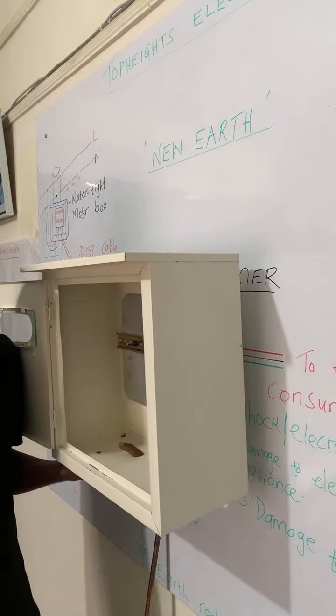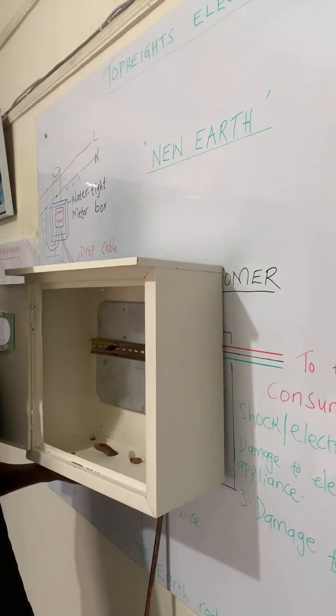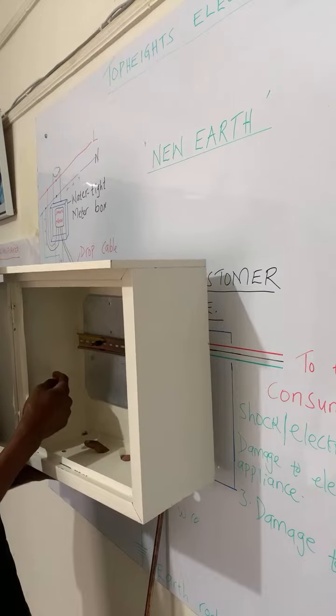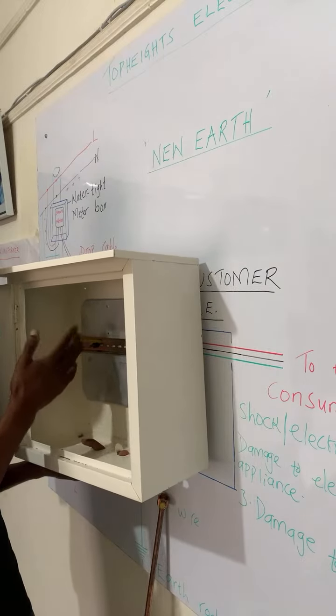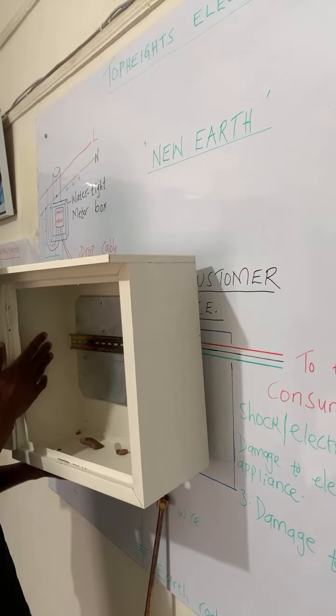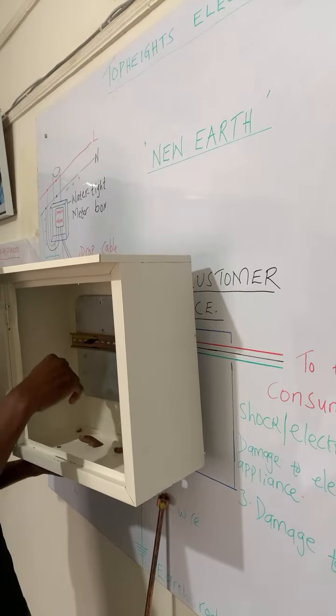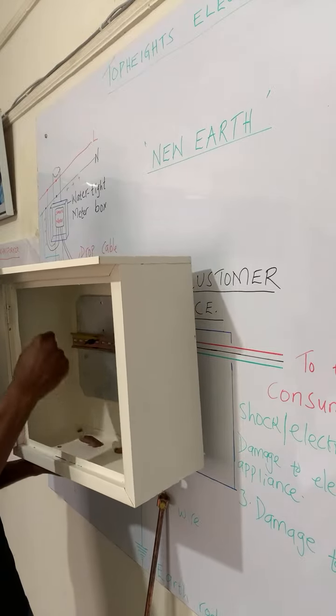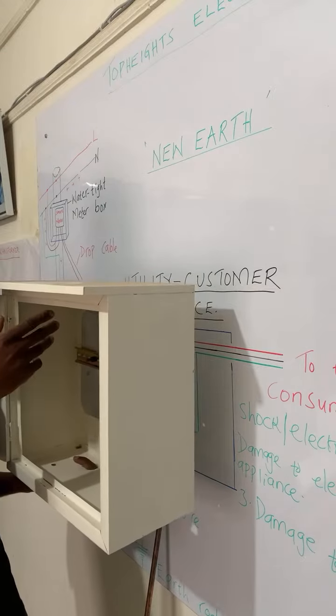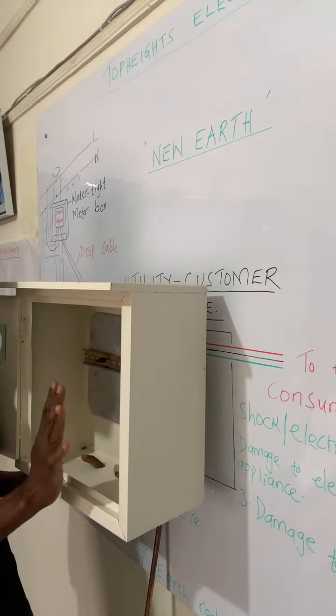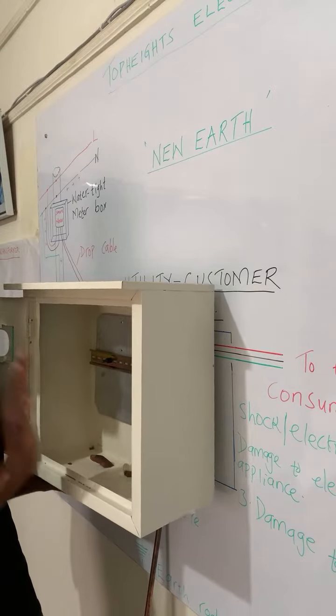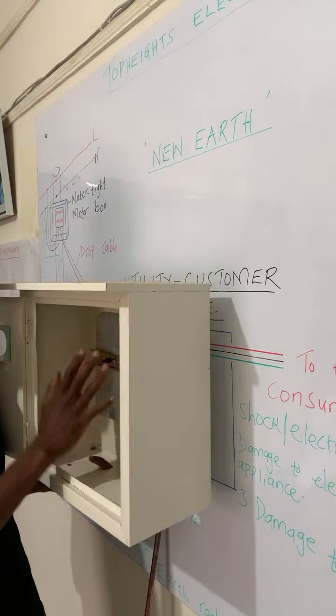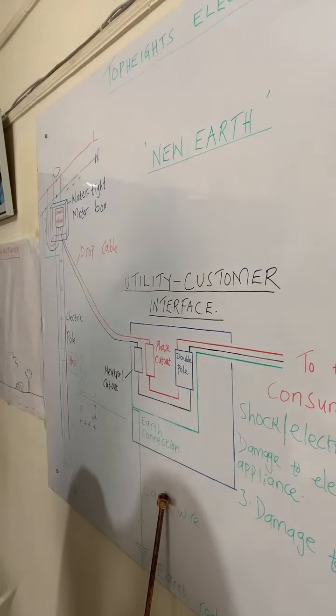Okay, so the earth connection will be started from the metallic point of the meter box, and then all the way to the earth rod, and then from there it will go direct to the consumer unit. So the neutral and the earth connection will not be bonded in the meter box or in the consumer unit.